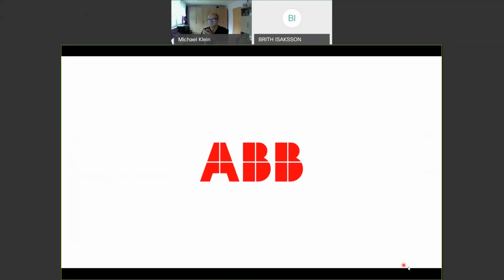Thank you. The third question coming up here is, because this is sitting on the roof and the weather conditions might be very different, does it fulfill IP66? Oh yes, absolutely. It has a stainless steel conduit box on top of that, and it is definitely an IP66, and it's quite easy to achieve. You remember the design of that motor. It's a totally enclosed motor. There is only one shaft end coming out, and that's what we are protecting with this Inpro Seal, that upgraded Inpro Seal. So yes, it is an IP66 enclosure. Okay, thanks.